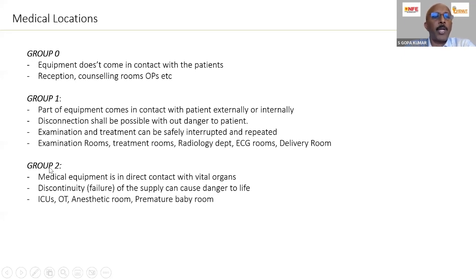Then the most critical ones are the group 2 medical locations, where medical equipment is in direct contact with vital organs. That means the medical equipment or conductive fluids are bypassing the skin. It is sometimes in touch with the heart. Even a very small voltage could be fatal. So with respect to criticality, these three groups are specified: group 0, group 1, and group 2 locations. Now, in order to get safety for a medical location, it is not one subject, unfortunately.